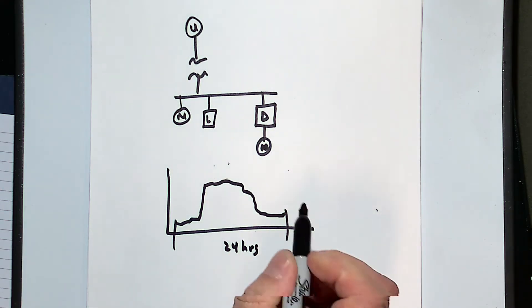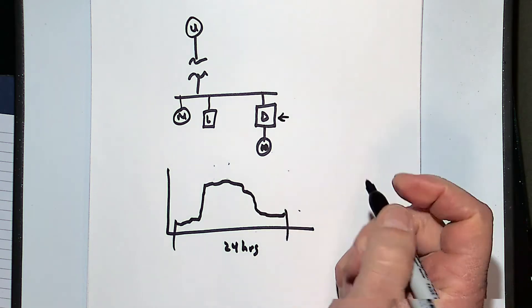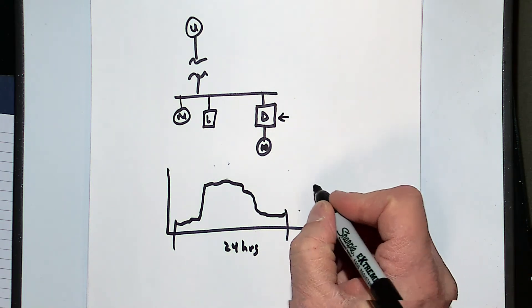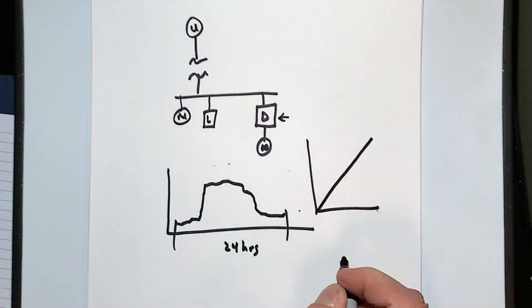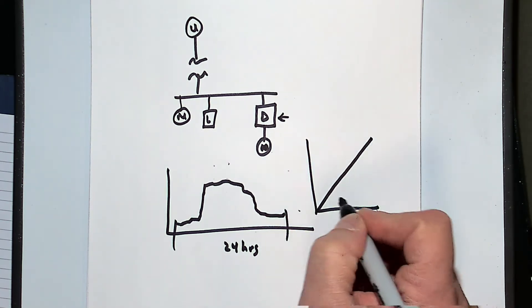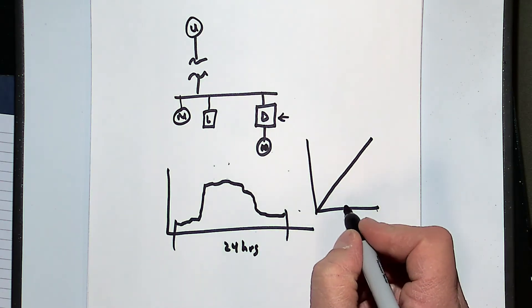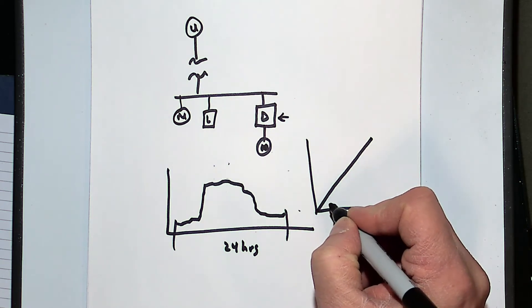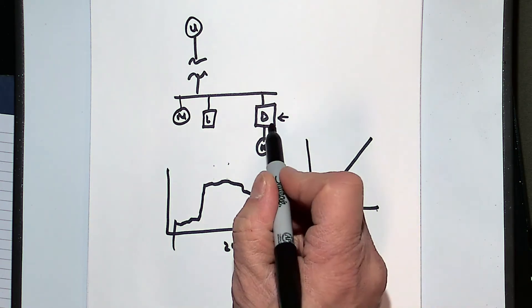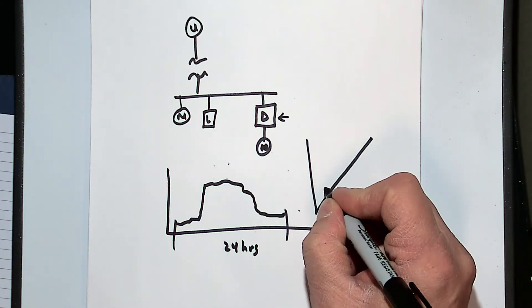But what happens is the 60 hertz current kind of follows that pattern. What's very interesting is the harmonics for VFDs and other loads like that don't really follow that linear progression. So as I add more load, my percent changes like one-to-one. What happens with drives is they're very, very heavily front-end loaded with harmonics.